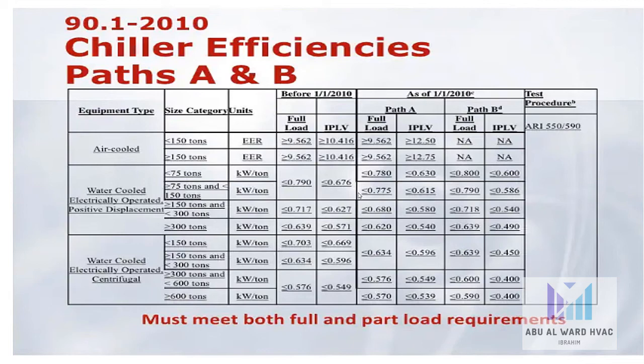the efficiencies of the air-cooled and water-cooled, which is electrically operated. Either it is positive displacement type or centrifugal type, and we can see the best type among all of these is the centrifugal type, water-cooled, especially in the part load condition, compared to the positive displacement as well as the air-cooled type.